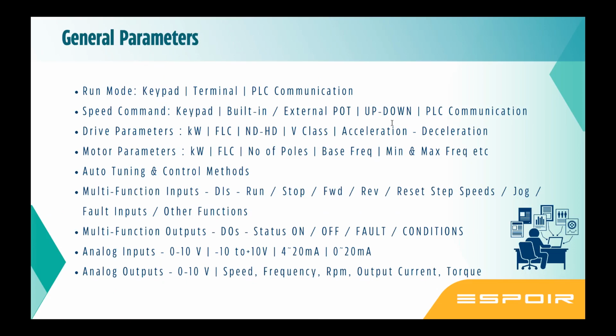Now the drive also gives you an analog output, 0 to 10 volt. This output is primarily for monitoring. It can give the equivalent output in respect to a speed or a frequency or an output current or a torque. So this you can define. Not every brand gives it, but certain brands, advanced models, give a torque output also. So you can choose whether you really need a torque output, then you need to select the VFD accordingly. So these are all certain aspects of general parameter setting.